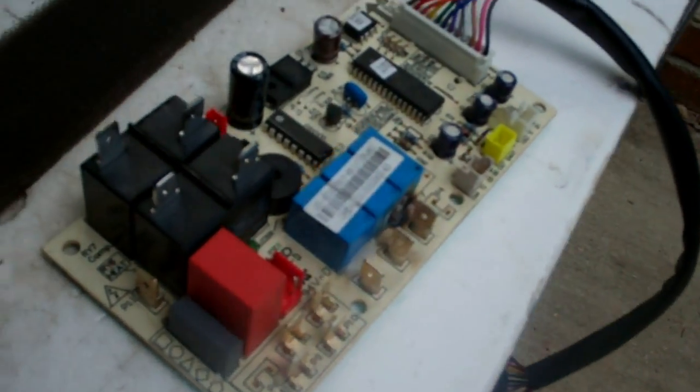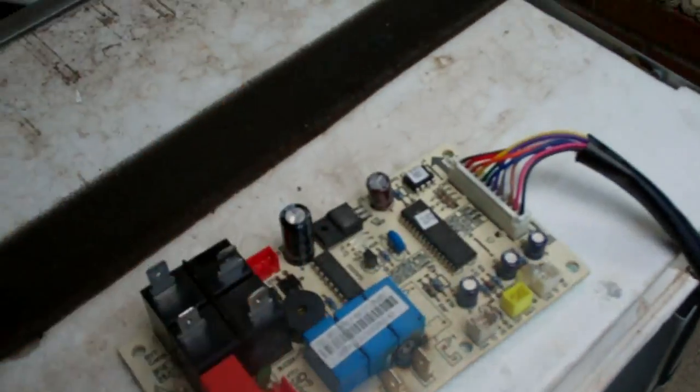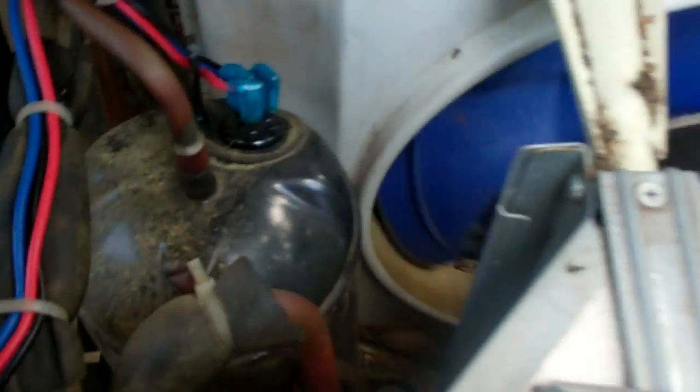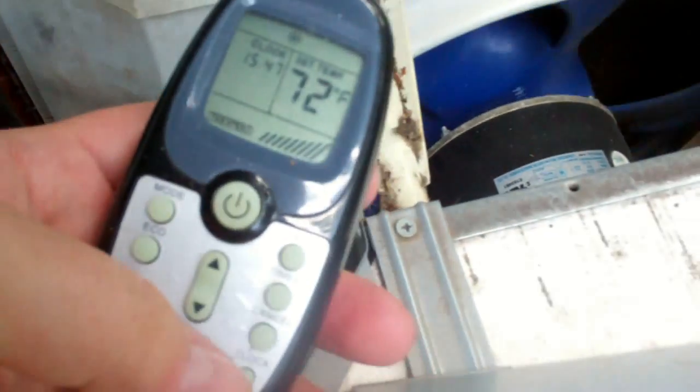The only relays I see are on this board. This is a brand new board. These are basically the same relays here and I don't see any scorch marks on them, just on these smaller relays that go to P1, 2, and 3, and that's the fan motor.